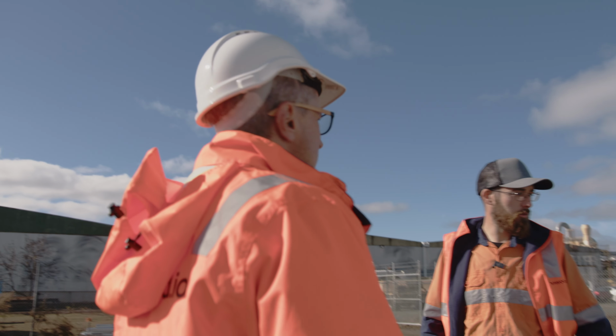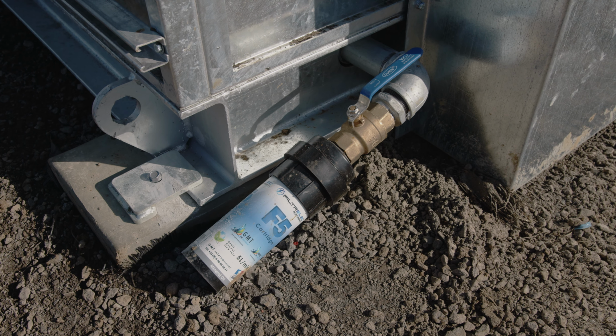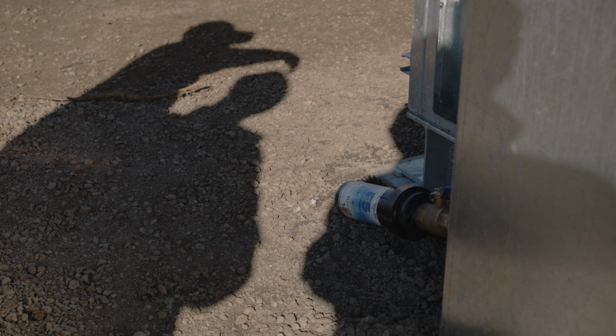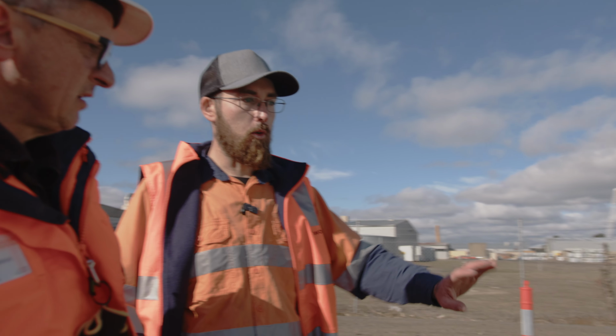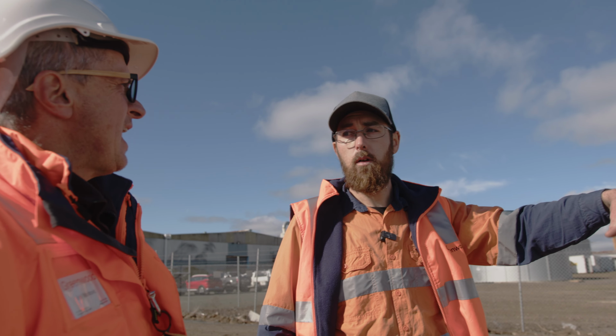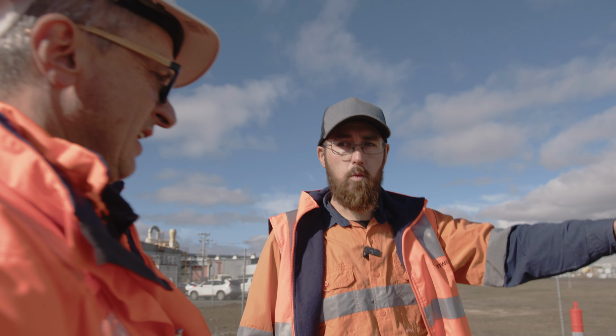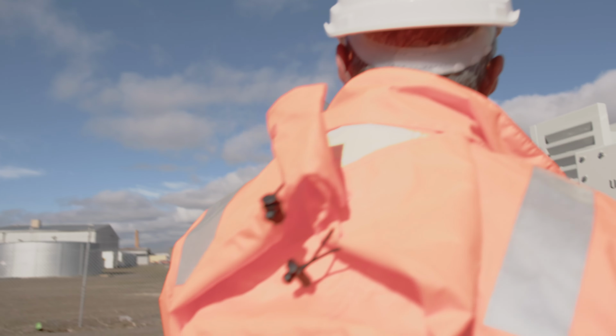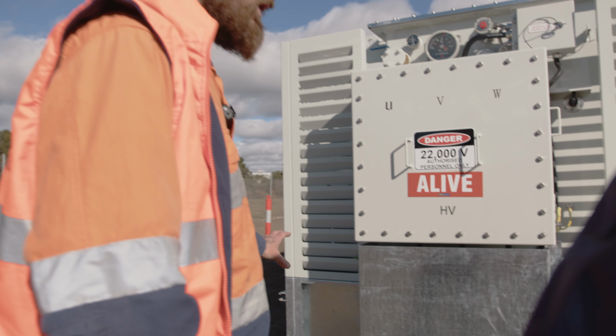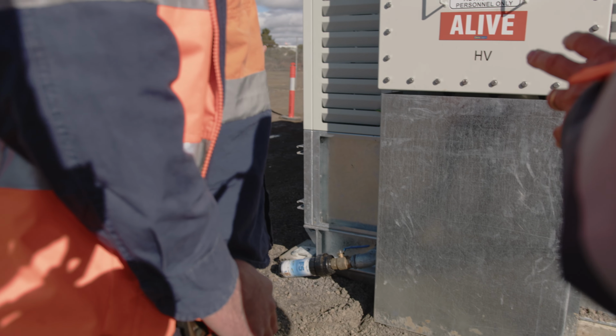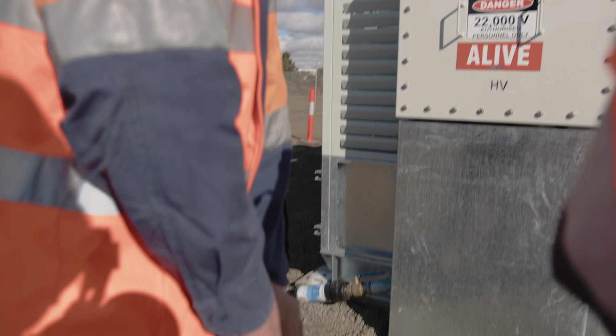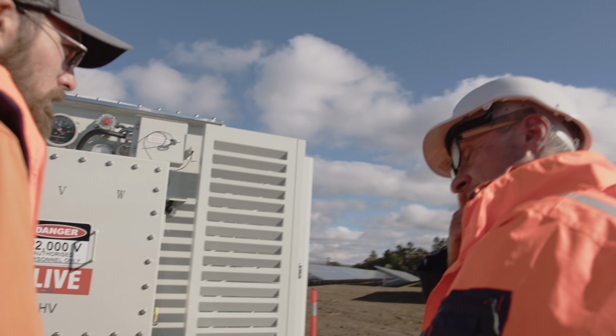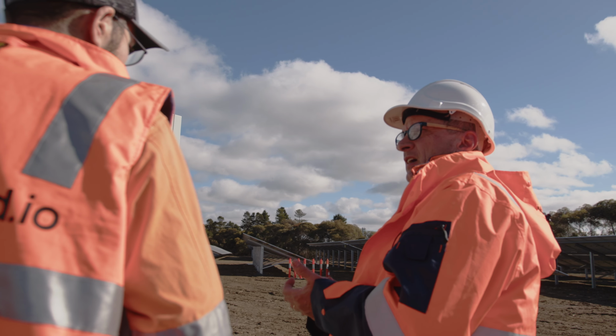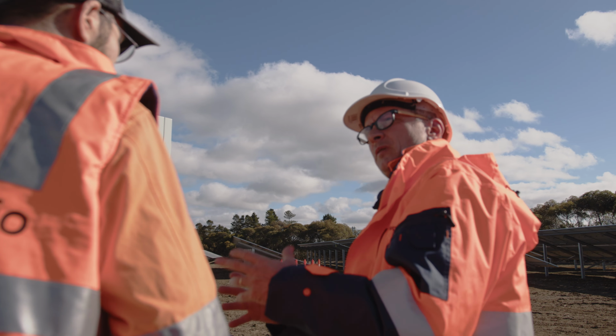Speaking about the leaking factor, you'll notice that we've got a water filter here. This is always left in the open position. The idea of this water filter is that if the bunding becomes full of oil, this filter won't let oil through, because we leave it open all the time for any rain. So if there's any rain in the area, that's going to land in the bunding as well. To prevent the bunding from filling up with water, it'll filter through this filter and out onto the ground. However, if oil gets into this particular filter, it will clog itself up, restricting the flow of any further oil.